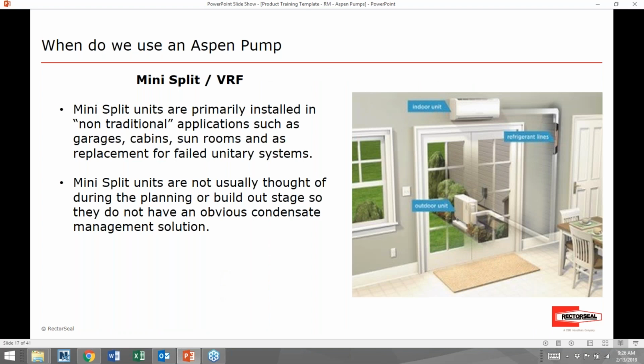So when exactly do we use an Aspen pump? We use Aspen pumps on mini splits and VRF units. Mini split units are primarily installed in non-traditional spaces. Applications can include cabins, sunrooms, a garage, and often they are used as replacement for failed unitary systems. Mini splits are not usually thought of during the planning or build-out stage, so there's not always an obvious condensate management solution. So that's why we need pumps from time to time, or to get creative with the drain lines.